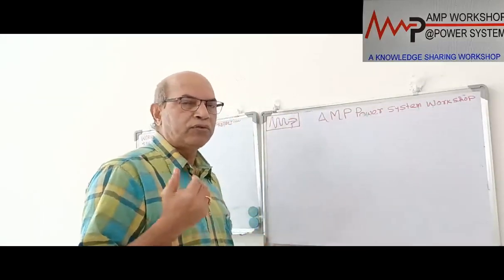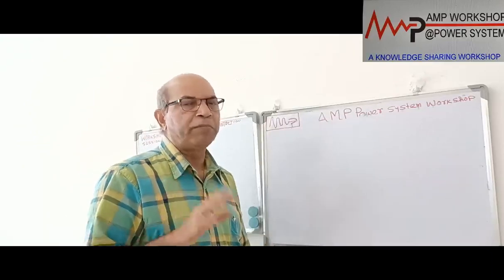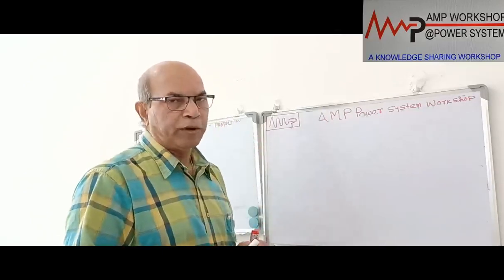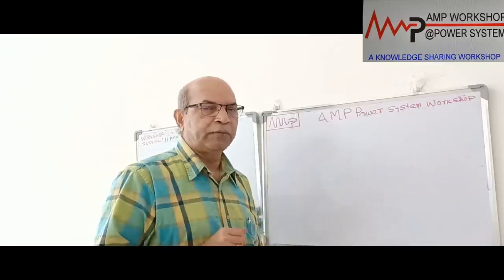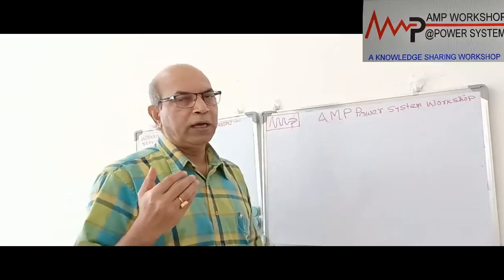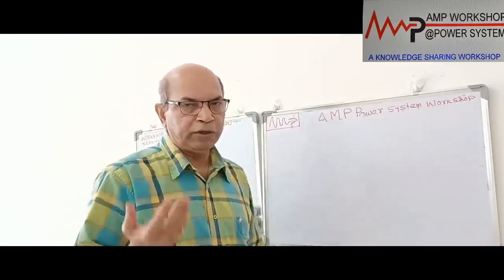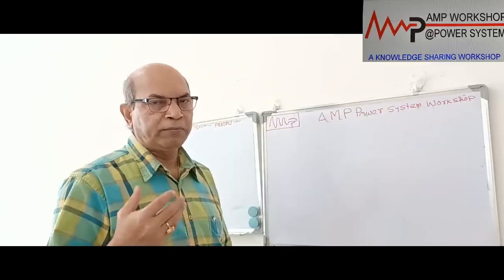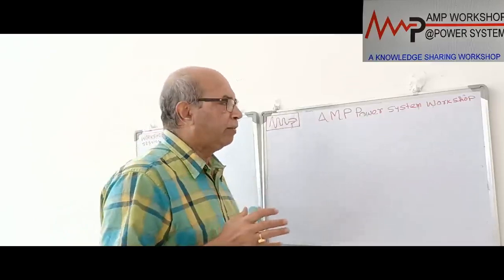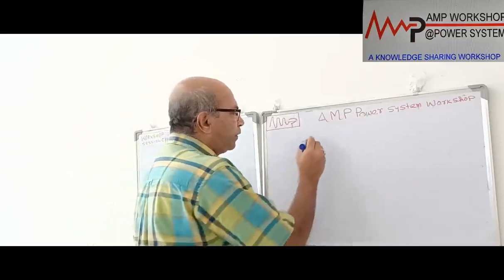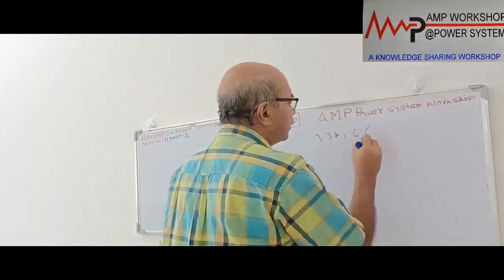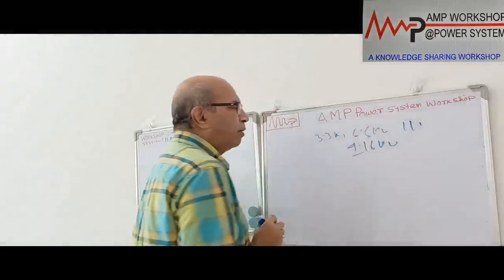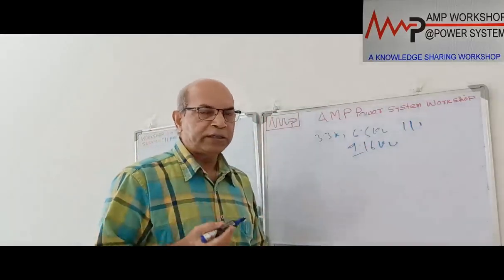Now we will go to the switchgear which is more than 1 kV but 11 kV or below. For that scheme, we cannot rely on the overcurrent protection. We can provide the overcurrent scheme, but that overcurrent scheme will work as a backup. When we go to more than 1 kV, that means 3.3 kV or 6.6 kV or 11 kV, or in the US system 4.16 kV. If we go to this voltage level of switchboard, in that case we cannot provide a full differential scheme.